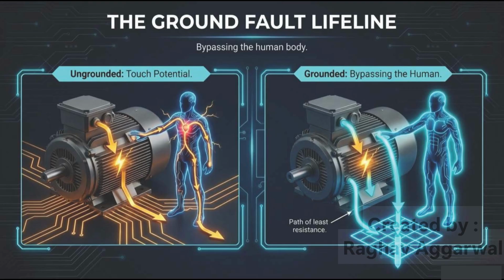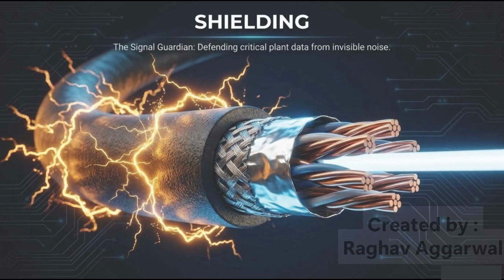In an ungrounded system, a person may become part of the path through which fault current flows. This creates a dangerous touch potential. In the grounded example, fault current follows a dedicated low-resistance path. Electricity naturally tends to follow the path of least resistance. By providing a controlled conductive path, grounding reduces the likelihood that current will use a human body as its route to Earth. Protection systems should guide fault energy away from people and toward engineered paths specifically designed to handle it. In industrial facilities, this concept contributes significantly to electrical safety and helps reduce the risk of injury during abnormal operating conditions. The next concept is shielding.